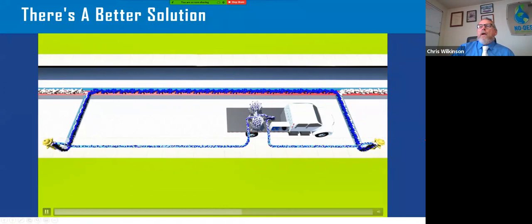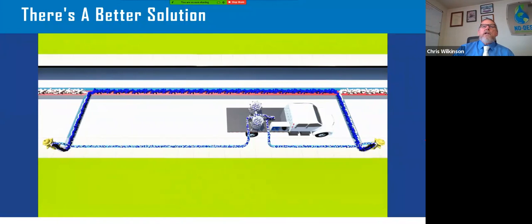So the water that was originally going down the main to serve the customers down here cannot flow through the pipe with 5 feet per second charging up the main here. That water has to go through our process, through the 1 micron absolute filters, and then back out. You can see that small amount of water that was being used continues on, while the bulk of the water scours the inside of the main and starts picking up the dirt. So now you can see it starting to pick up the dirt.